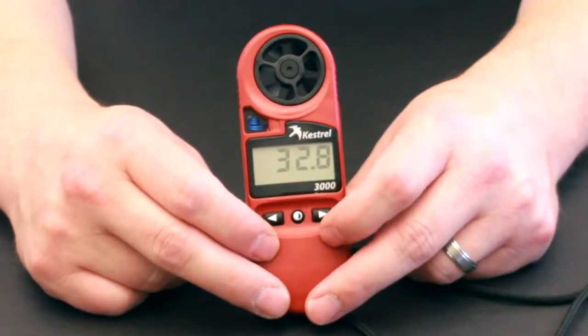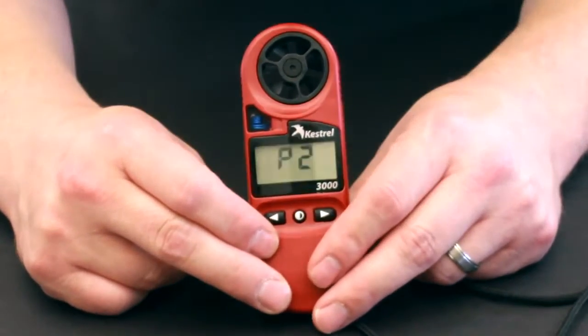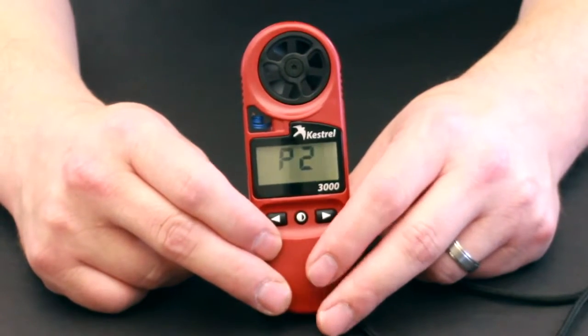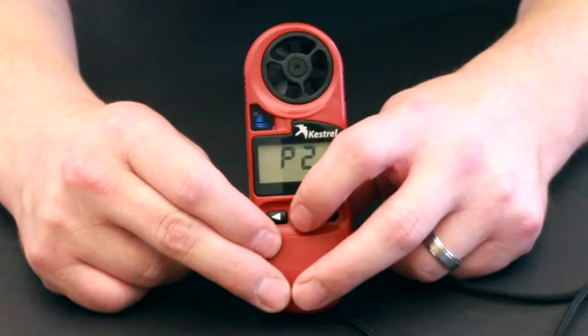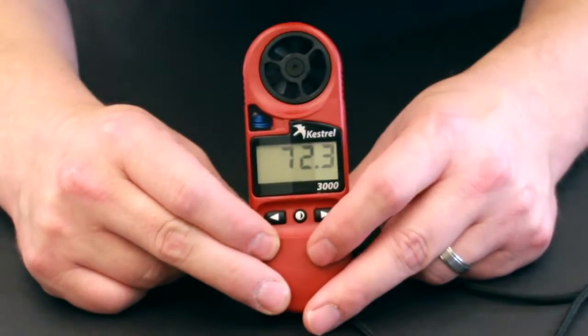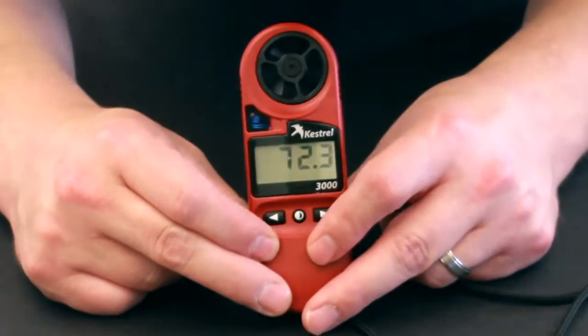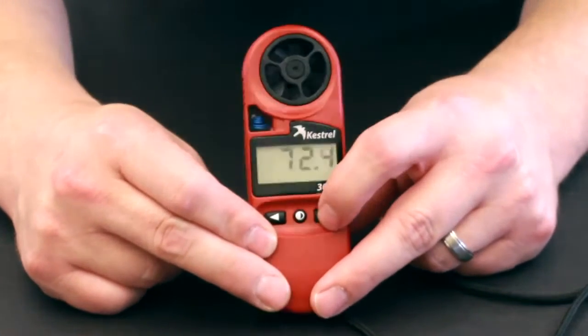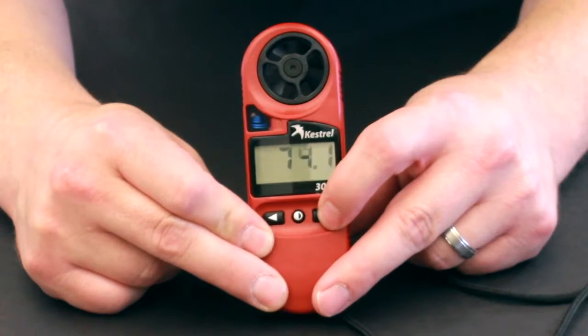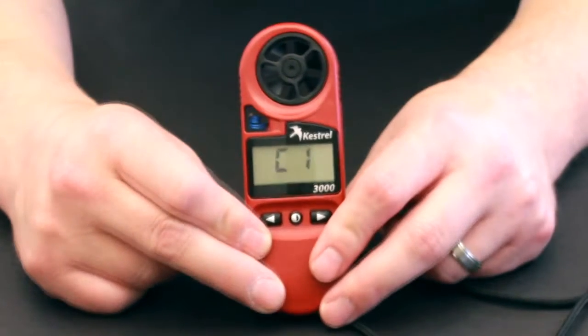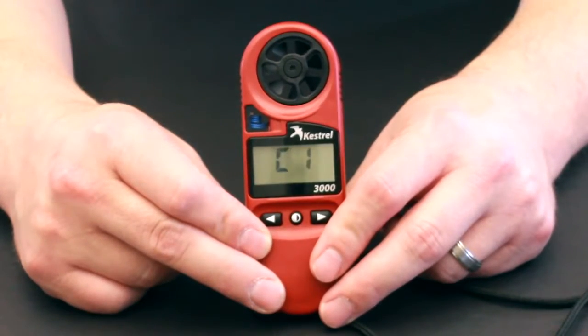Once we have that, we'll hit the center button to move to the second value, which is P2. This is going to be the value of the sodium chloride chamber. Let's hit the center button, and it says 72.3. We want this to be 75.3, as noted in the instructions, so let's increase this until we get to 75.3. Now, we'll hit the center button. Now, we're ready to start the humidity calibration.